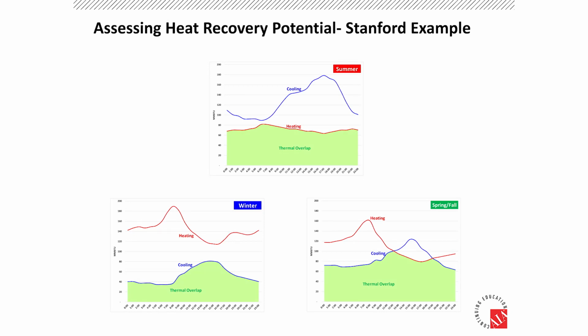When you look at it on a daily scale, here are 3 examples from Stanford: summer, winter, and the shoulder seasons. You can obviously see the higher cooling peak in summer, but there's still a consistent amount of heat needed in summer for hot water for dorms and buildings, and for tempering cold air back up to the temperatures we want in buildings. That thermal overlap, shown in green, is the opportunity for reusing heat with a heat pump rather than making it new by burning gas. You can see for the other two seasons that throughout the year there's always some amount of heat overlap, or heat overlap need.